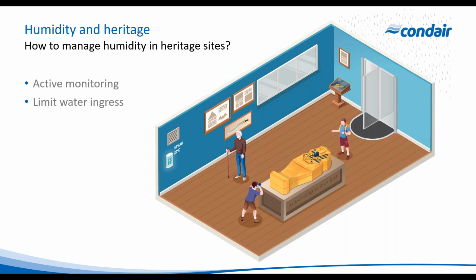We also want to limit water ingress using revolving doors or vestibules. Don't open windows. However, as already mentioned, building regulations specify a level of required ventilation. And in the UK, that's 10 litres per person per second. So keeping the outdoors out is never going to be a comprehensive solution to humidity management.